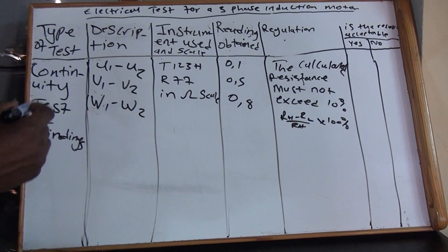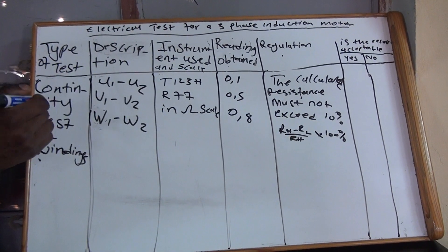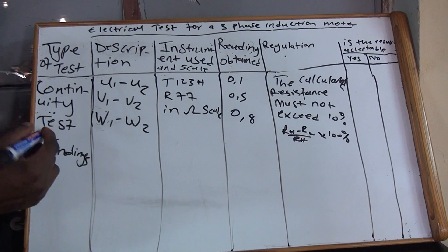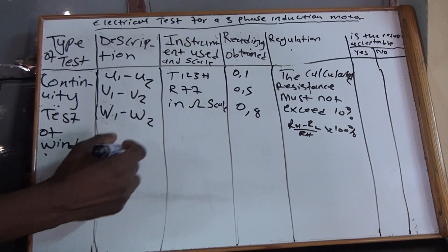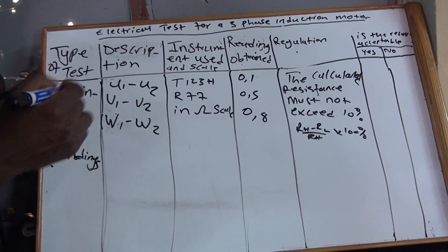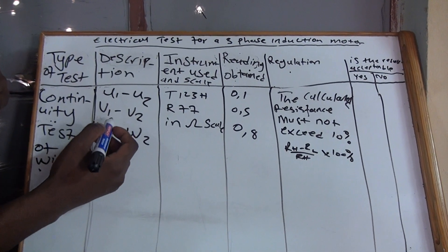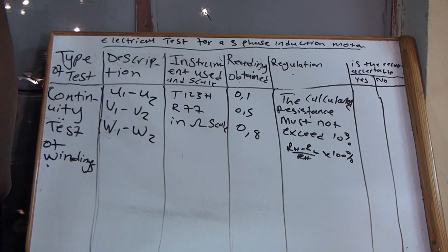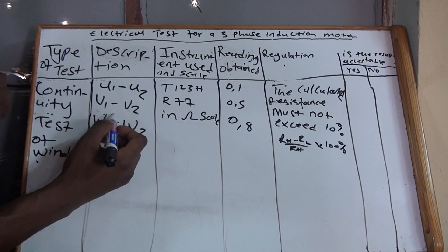The first test we're going to do is the continuity test of windings. You must write this on your paper — when they give you the sheet they will not write it, you will write the type of test. On the description you are writing what you're going to test: from which point to which point. You are going to test between U1 and U2, then V1 and V2, then W1 and W2.